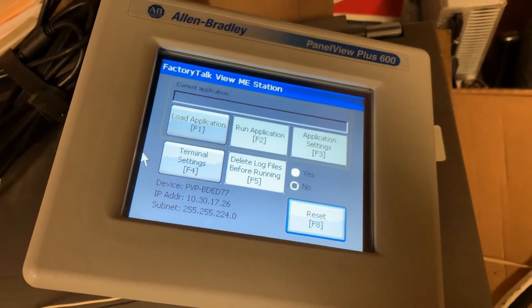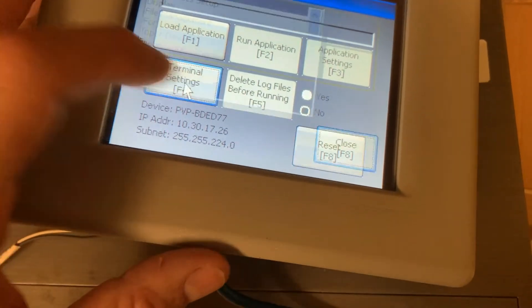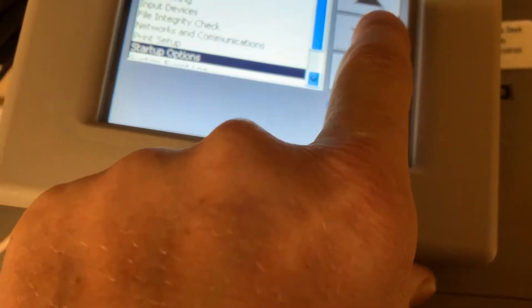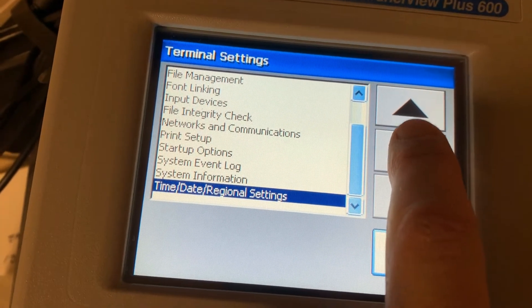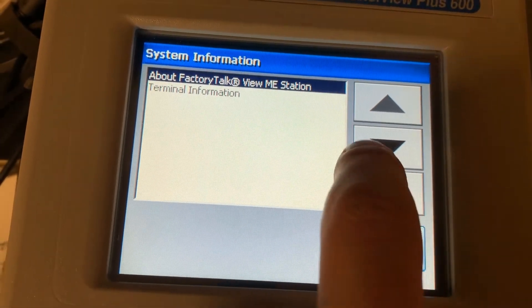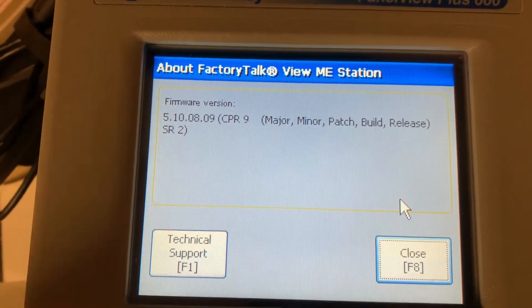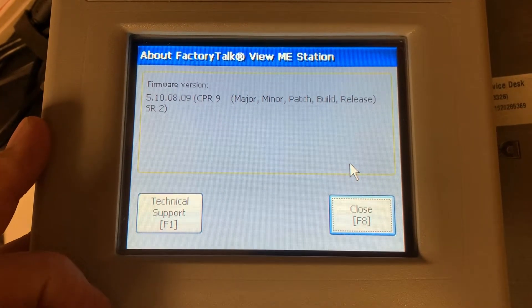We've got a Panel View Plus 600 and we're going to be upgrading the firmware on this. First we're going to check and see what we've got in it right now. We'll go down to our system information, select 'About,' and it'll give us our firmware version. Right now this one is on 5.10.08.09 and our version is 12, so we're going to upgrade this to 12.